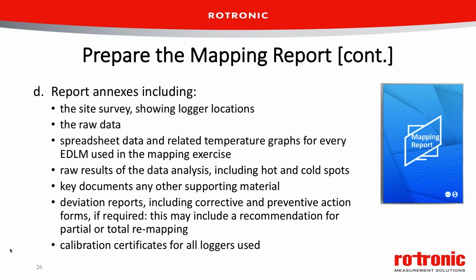The last section of the mapping report should have an index containing the site survey showing the logger locations, the raw data, the spreadsheet data and related temperature graphs for every logger used in the mapping exercise, raw results of the data analysis, including hot and cold spots, key documents and notes prepared during the mapping exercise together with any other supporting material.